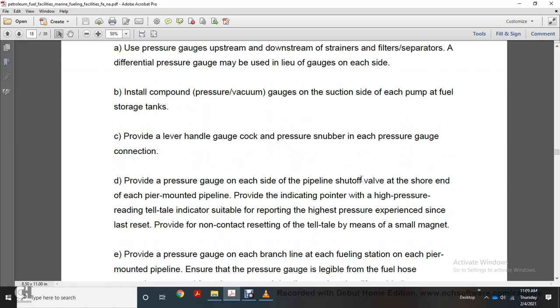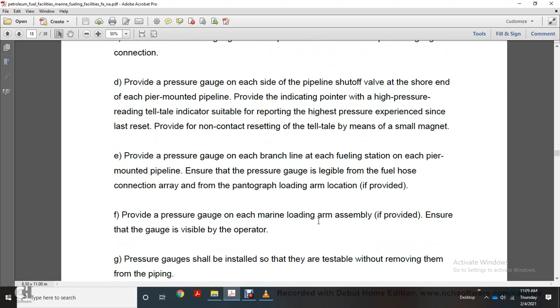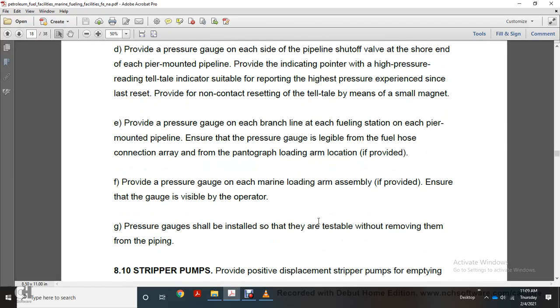Provide a pressure gauge on each side of the pipeline shutoff valve at the shore end of each pier-mounted pipeline, provided with an indicating pointer with a high pressure reading telltale indicator, reporting the high pressure experienced since the last reset. Provide for non-contact resetting of the telltale by means of a small magnet. Provide a pressure gauge on each branch line, each fueling station, and on each of the pier-mounted pipelines.